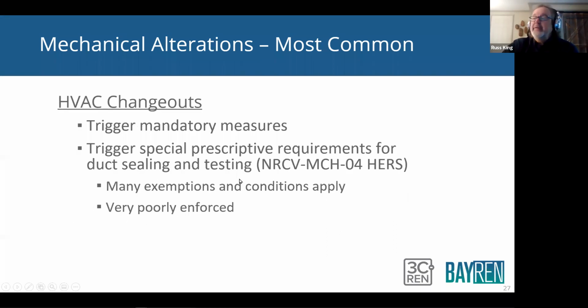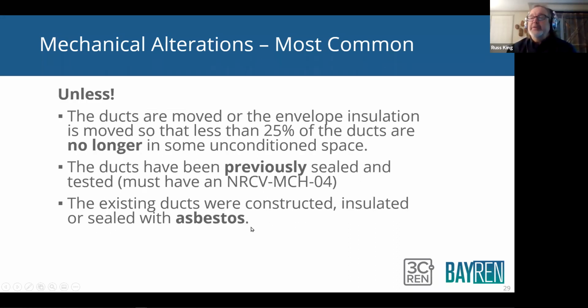That's that form. If you forget those things, the NRCV-MECH-04-HERS has that list. And then there are some exceptions. If the ducts are moved so that they're no longer in unconditioned space, that actually happens. They move the insulation or they move the ducts so that they're within conditioned space, and you don't have to seal them anymore. Sometimes it's easier to do that than it is to seal the ducts. If the ducts have ever been previously tested and sealed and they have an NRCV-MECH-04 for that system, if they make changes again, they don't have to do it a second time. So that's interesting. And then last but not least, asbestos. If you see somebody claiming asbestos, I highly recommend that you verify that there's actually asbestos on those ducts, okay? That exception gets abused quite a bit. They'll just say, oh yeah, there's asbestos, so we don't have to seal it. And there's not. Unfortunately that happens quite a bit. So that's an exception.